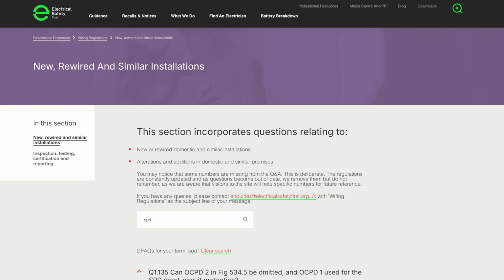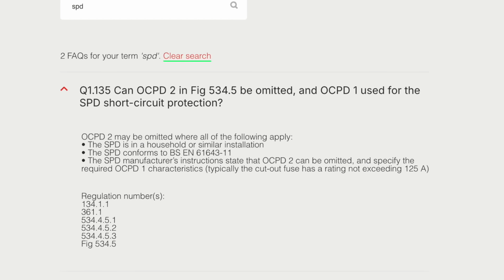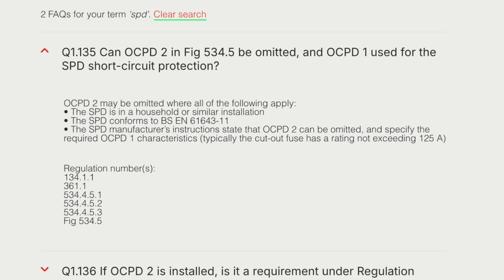Electrical Safety First, the NICEIC-backed consumer advisory body, says that the Type 2 overcurrent protection can be omitted in domestic properties if 2 conditions apply. First, that the SPD conforms to BS EN 61643-11, and second, that the manufacturer's instructions say it's not necessary and it specifies the Type 1 overcurrent protection characteristics. The latter is typically that the cutout fuse has a rating not exceeding 125 amps.